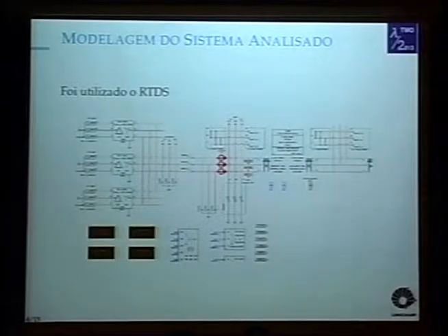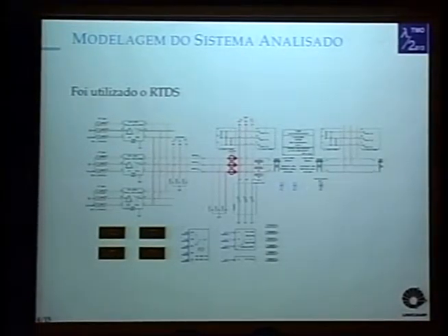In addition, we implemented a component in our RTDS which allows for the calculation of the apparent impedances for a previous analysis to the relay test. It was implemented using the C language, and we use sampling, calculation of the phasors, voltages and currents, and also the impedances.